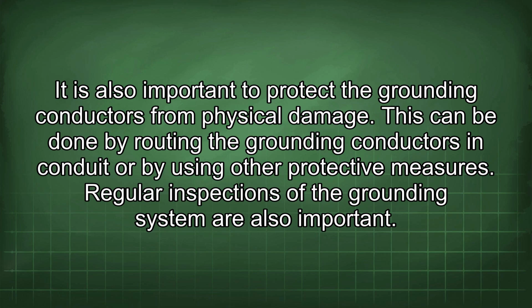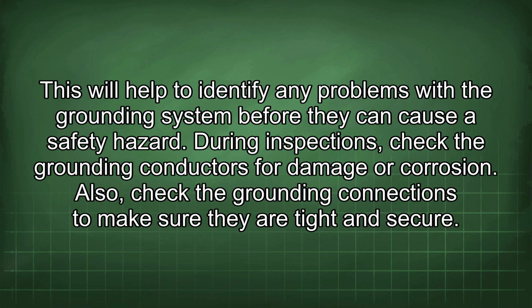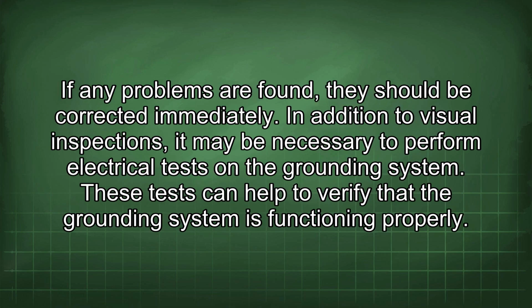Regular inspections of the grounding system are also important. This will help to identify any problems with the grounding system before they can cause a safety hazard. During inspections, check the grounding conductors for damage or corrosion. Also, check the grounding connections to make sure they are tight and secure. If any problems are found, they should be corrected immediately. In addition to visual inspections, it may be necessary to perform electrical tests on the grounding system. These tests can help to verify that the grounding system is functioning properly.